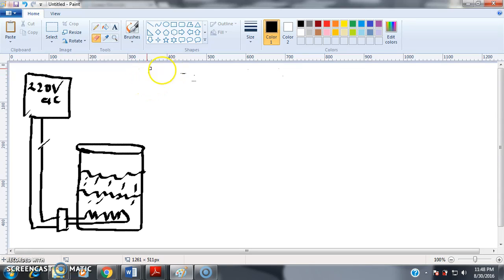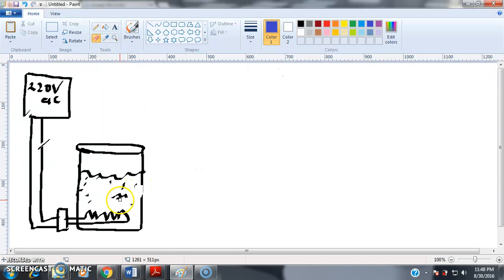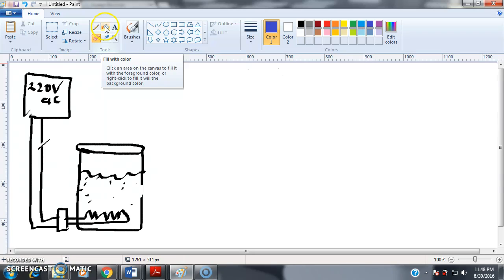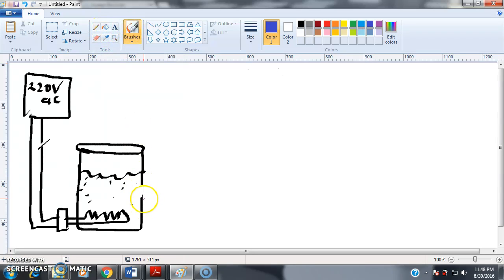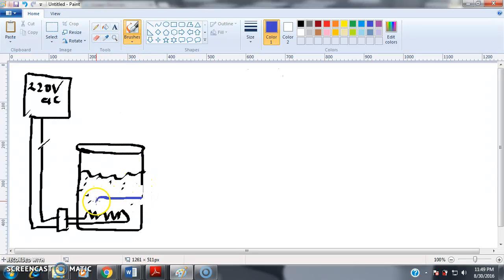So how do we connect our RTD to measure the temperature of the water in this tank? We need to put the RTD instrument inside what is known as a thermal well. When you design your tank, you need to install a thermal well — it's a metal fitting in the tank so that water never leaks out. Your RTD then goes inside the thermal well.